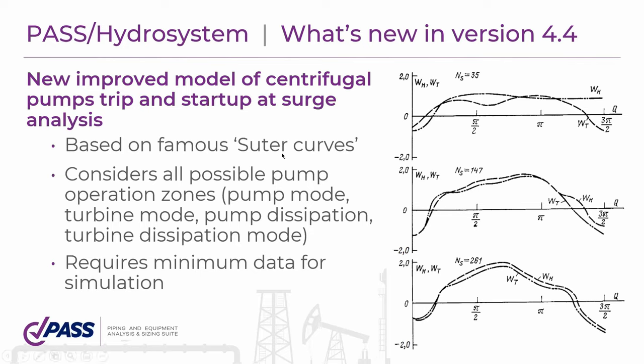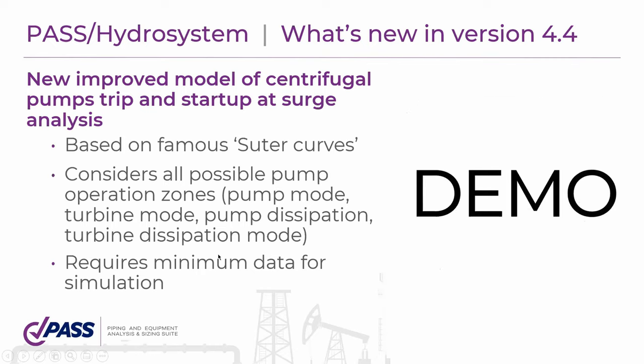This model is based on the famous Suter curves, experimental curves of different pump operation zones, and this model considers all possible pump operation zones like normal pumping mode, turbine mode, pump dissipation mode, turbine dissipation mode. And one important thing, this model requires minimum data for simulation. Once again, allow me to show you live in the form of a demo.